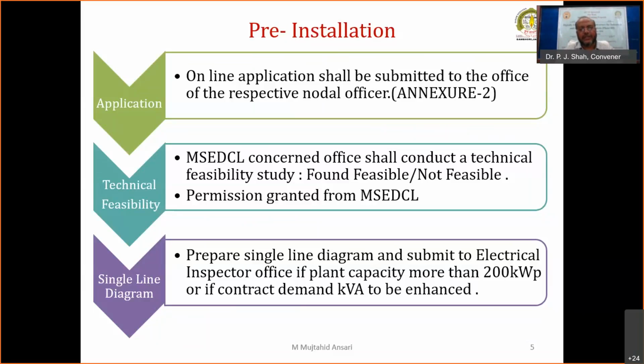This technical feasibility has to be obtained from the MSEDCL concerned department or concerned head where you are going to install the power plant, and permission is granted by MSEDCL. Technical feasibility consists of the capacity of the transformer. If you have your own transformer, then the capacity of the transformer should be enough. Second, the maximum PV power that can be installed should be equal to or less than the contract demand of the consumer.